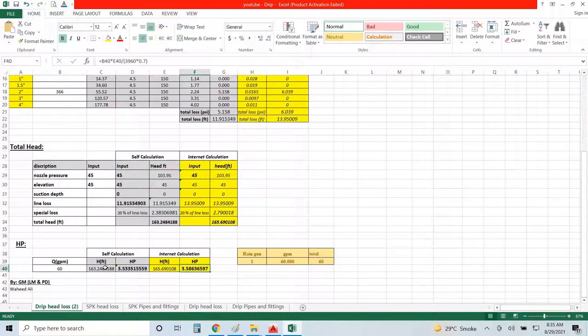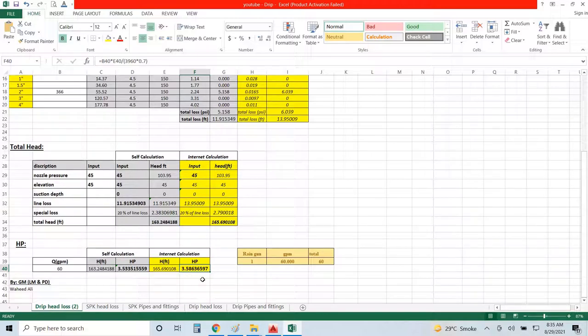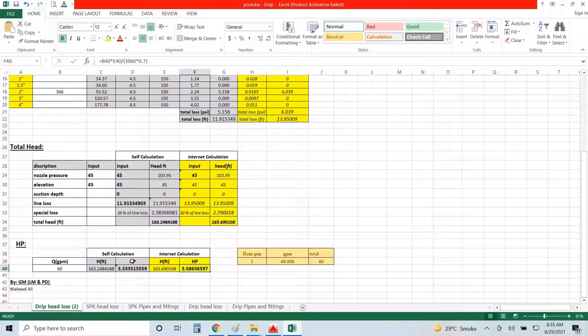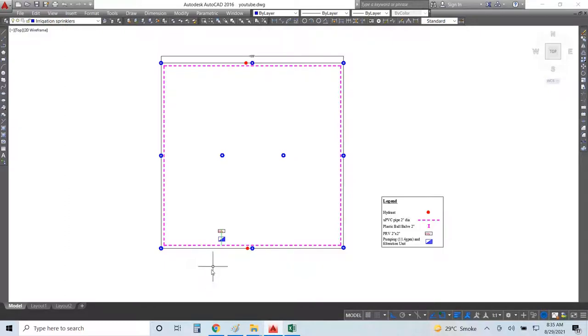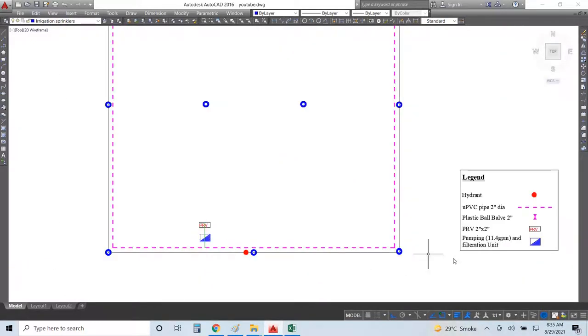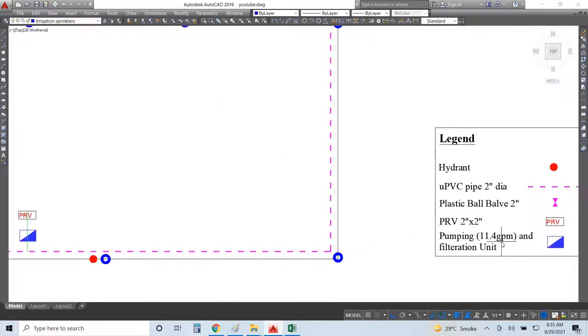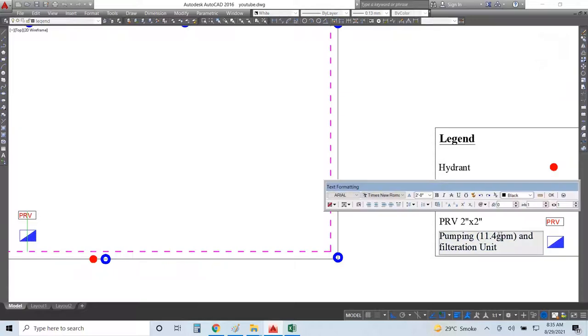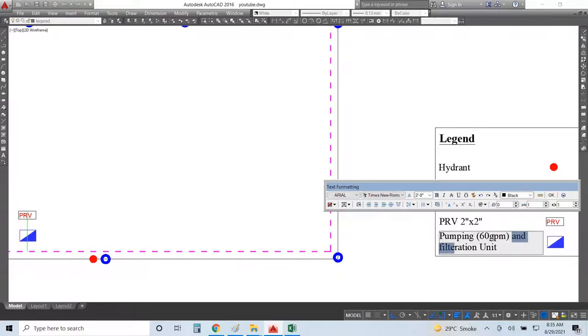This is not shut off head and this is not zero head water. 60 gallon you required at 163 feet pressure, so they will give you a reasonable pump. But according to my experience, you will get about 5.5 horsepower. This is now 60 gpm and you don't need the filtration unit here, so I will delete that one.